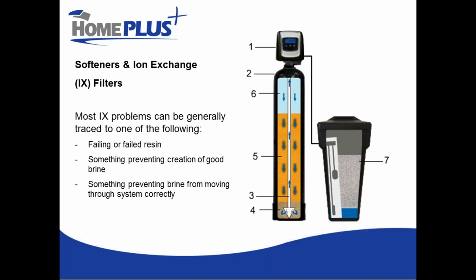So in the diagram here, we have number one at the top is the control valve. And again, that's just a fancy timer. Most often, they will also have a built-in or external water meter that counts the amount of water being processed by the system, which is really important. We have the media, which is number 5. That's the magic. That's the workhorse that's doing all the work. That media has a certain amount of capacity to remove contaminants. Once that capacity is used up, we need to regenerate the media to restore the capacity back as close to maximum capacity as possible. And we do that with salt brine.